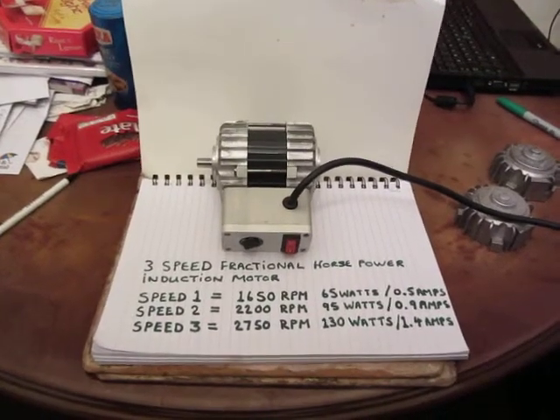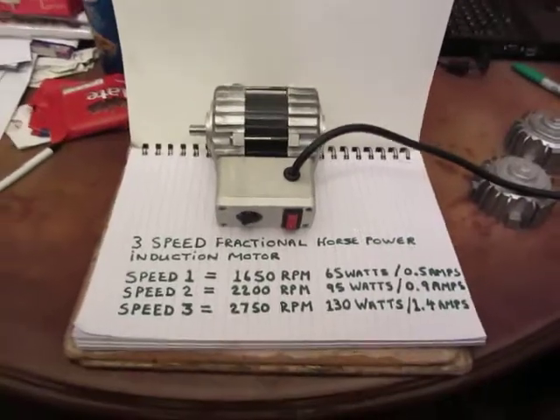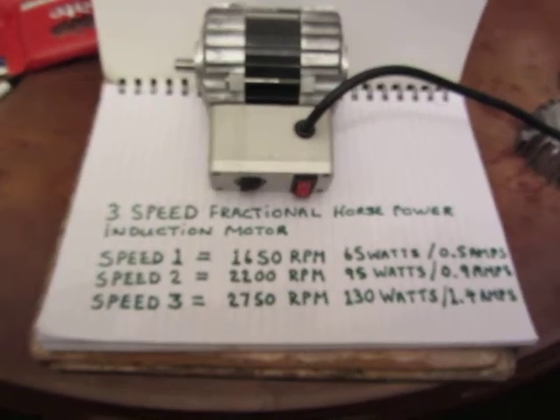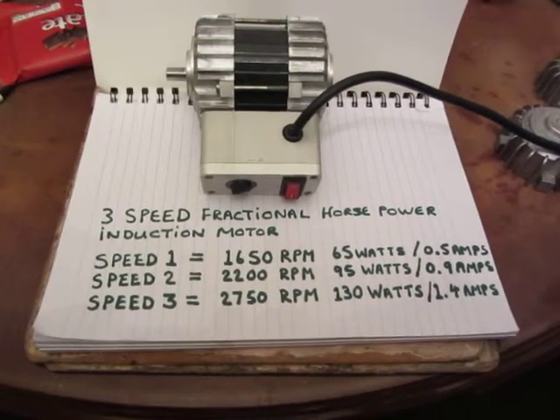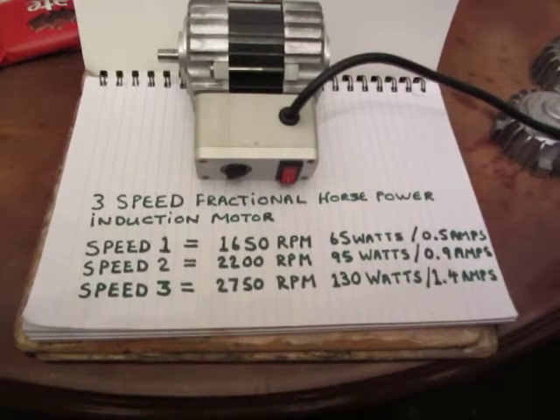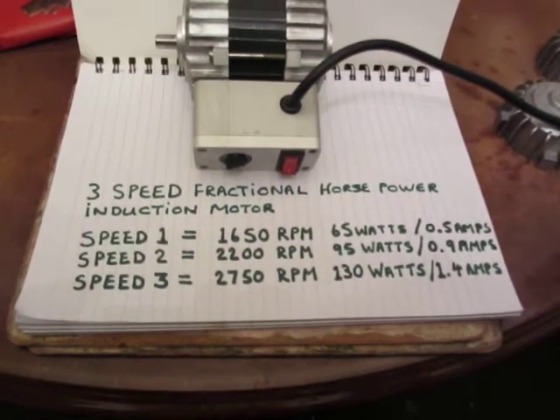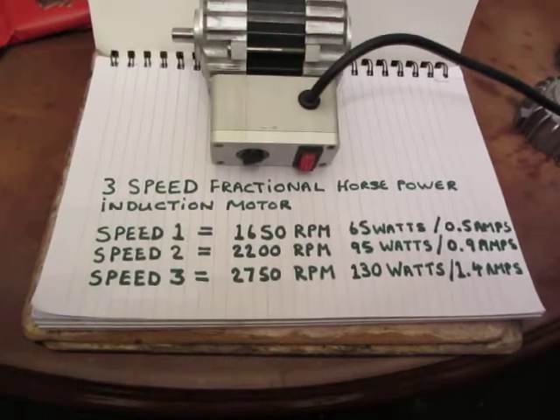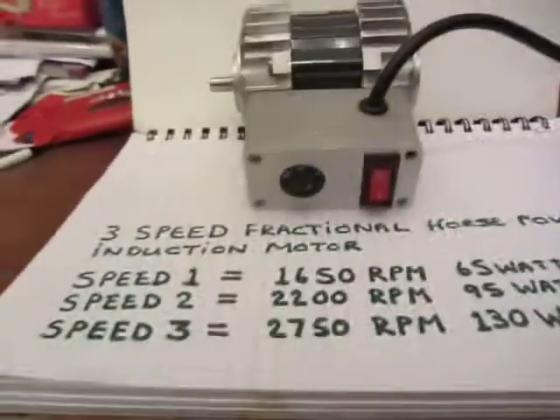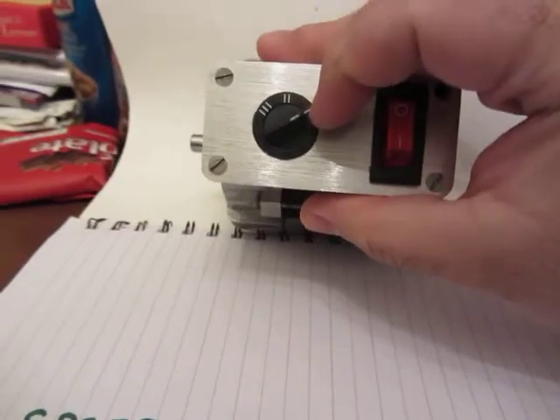Hi guys, it's Joseph D here. As promised, here is the video for the three-speed induction motor — the motor end shields I was casting last year, now being put together. Before we run the motor, here are the specs: three-speed fractional horsepower induction motor taken from a central heating circulating pump. Speed 1: 1650 RPM, 65 watts, 0.5 amps. Speed 2: 2200 RPM, 95 watts, 0.9 amps. Speed 3: 2750 RPM, 130 watts, 1.4 amps. Close-up, we have our illuminated on/off switch, speed selector, Speed 1, Speed 2, and Speed 3.